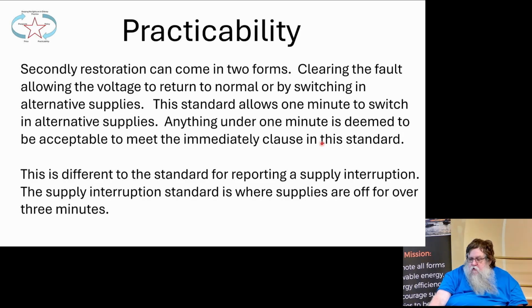So restoration can come in two forms: clearing a fault will allow the voltage to restore to normal, or switching in alternative supplies. So that's when your power's gone right off and then you switch in alternatives. And those alternatives can take different amounts of time. If they're automatic, it can be done in 10 or 20 seconds. If it's less than 1 minute to switch in alternative supplies, it doesn't count as a supply interruption.